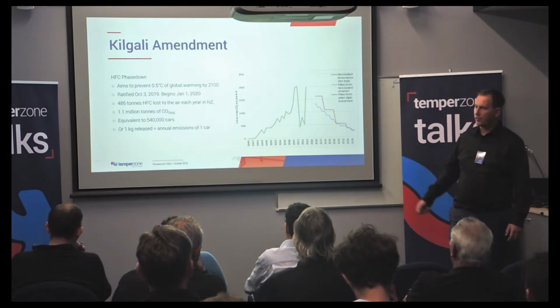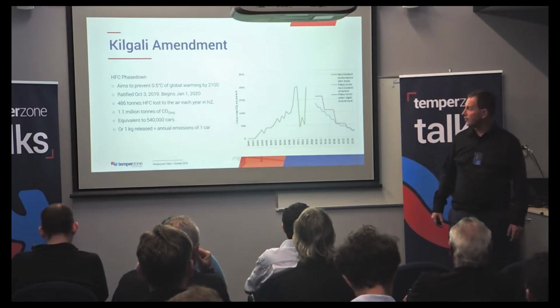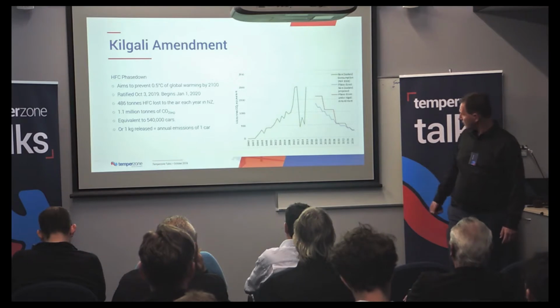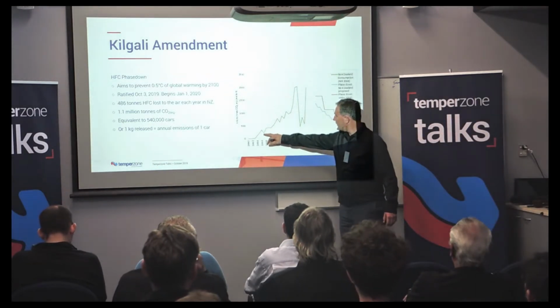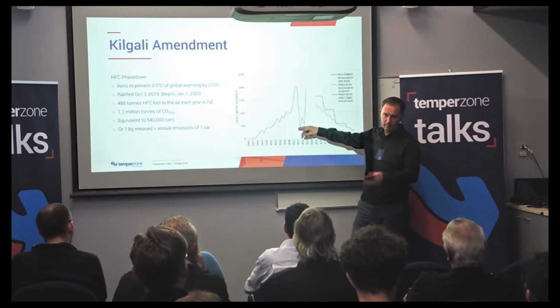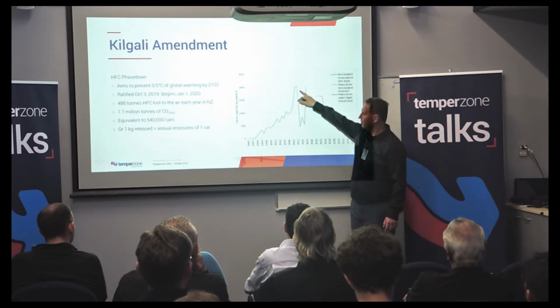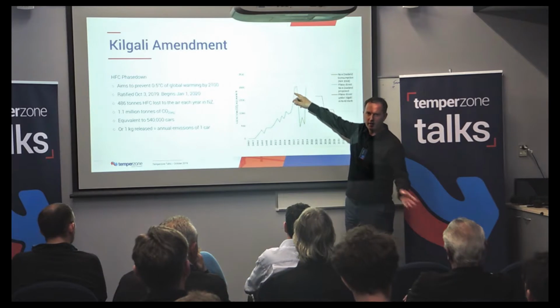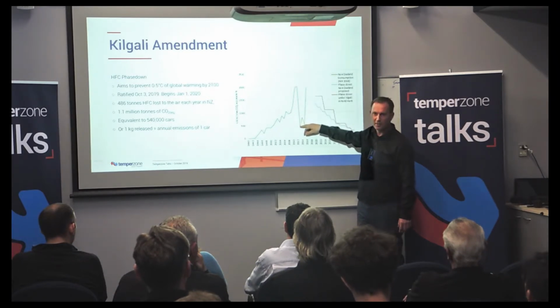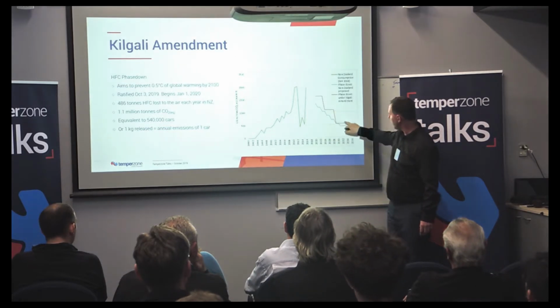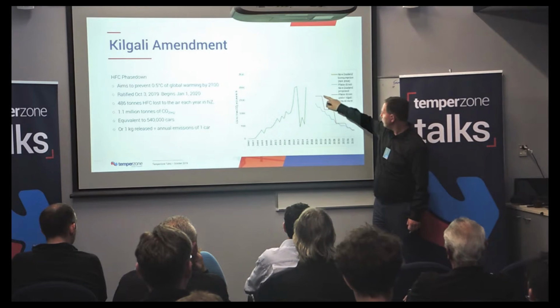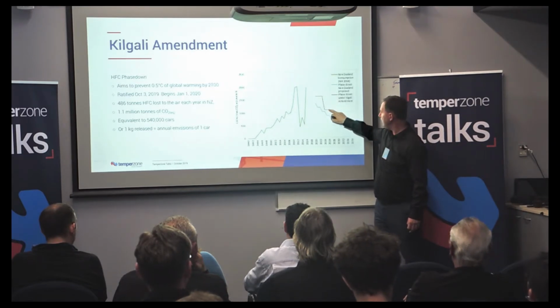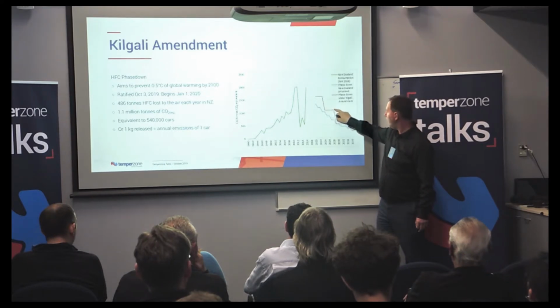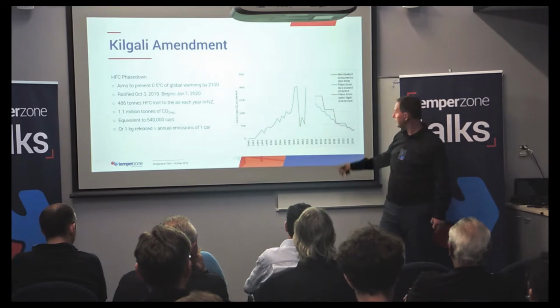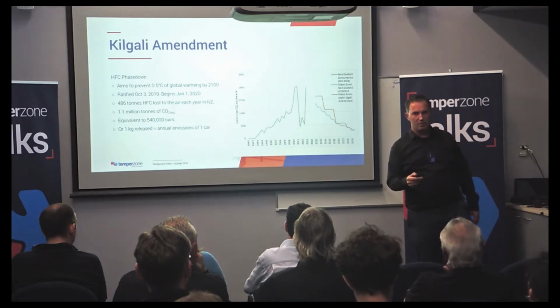This is based on R410A, a refrigerant like 404 or 407C. This is roughly twice that. So we've got here, it's not the nicest graph, but it's looking at HFC imports into New Zealand. This is for the start of the emission trading scheme and company stockpiled, which is why those are big reductions next year. But anyway, this is the Kigali Amendment phase down, and this is New Zealand's phase down path. This drop here basically means that we're coming out of R410A into a lower GWP refrigerant, and then we come out of those late 2020s to a zero GWP refrigerant.